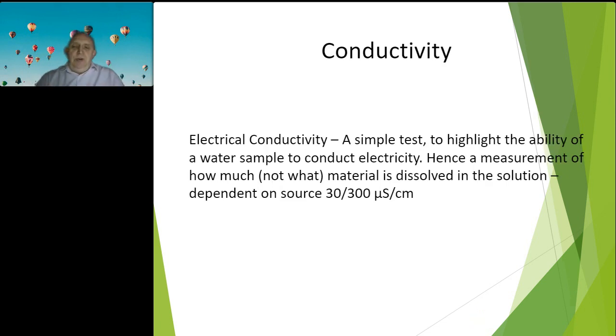Conductivity - is conductivity a major risk? Well, not on its own, but conductivity is a very simple parameter to check, a very simple parameter that we can test. We take a sample, we have a calibrated meter, we put the meter into the sample, and we can check the ability to conduct an electrical charge, and that gives us a reading. So in the UK, we check the conductivity on a weekly basis - we're checking our supply routinely. It's simple: if key properties of the water change, the conductivity will change. So we know whether it's an RO plant, whether we've got softening plant, we know something isn't right. And that tells us to get our maintenance teams in, and we have a look at what's going on upstream.